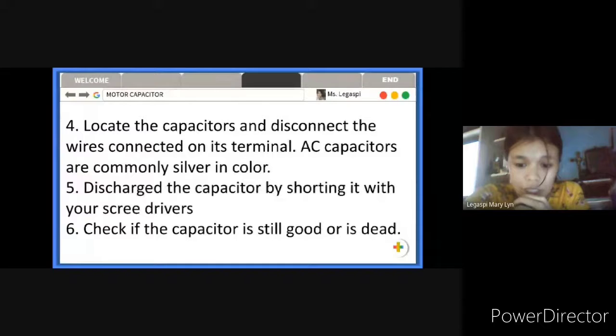The fifth step is to discharge the capacitor by shorting it with a screwdriver. Let the metal part of the screwdriver touch the common terminal and also the fan or herm terminal at the same time. This will create a closed circuit, discharging the capacitor.